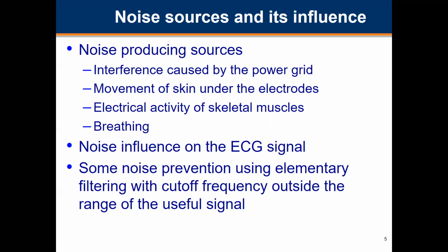Further, there is additional filtration with a low-pass filter with a cutoff frequency of 30 Hz. Since the QRS complex also contains higher frequencies up to 50 Hz, this type of filter causes a certain decrease in its amplitude. Tests show that this loss is negligible with regard to the benefits that this kind of filtering introduces in the techniques for segment detection. Apart from filtering, the implemented methods within the algorithm deal successfully with noise themselves, which will be presented in the forthcoming slides.